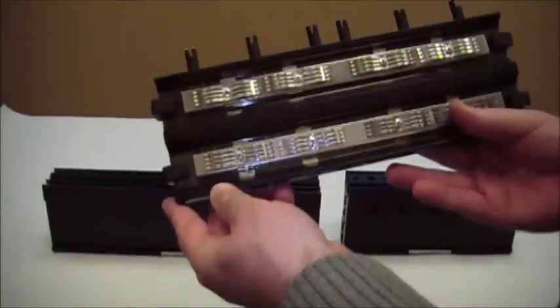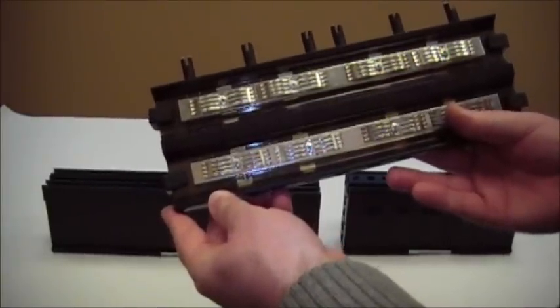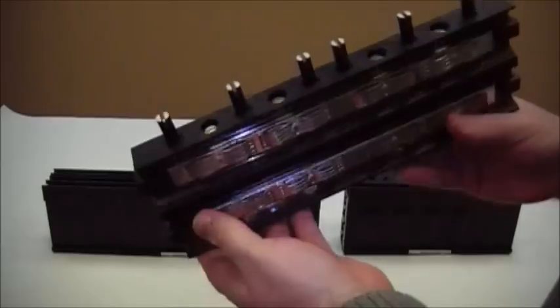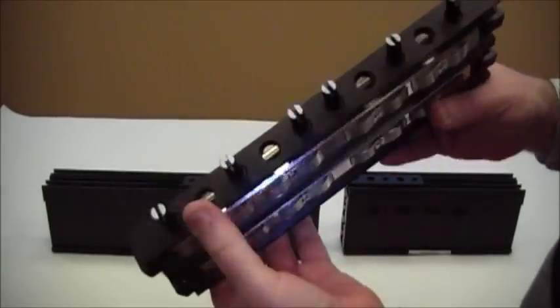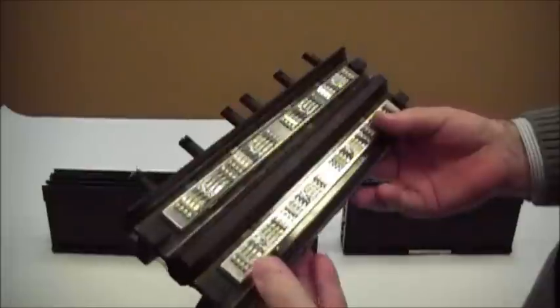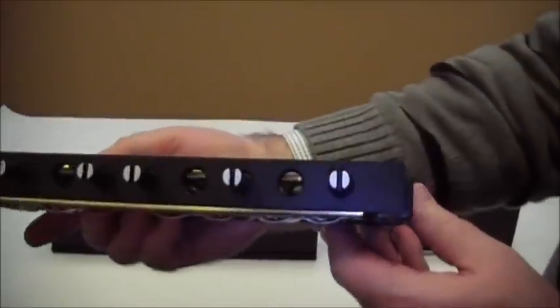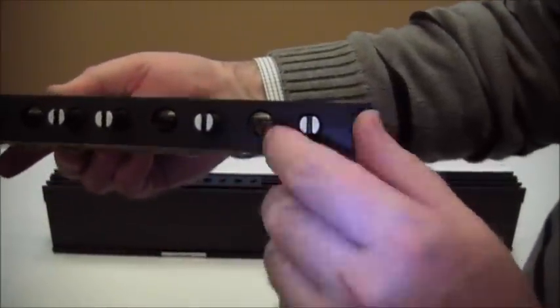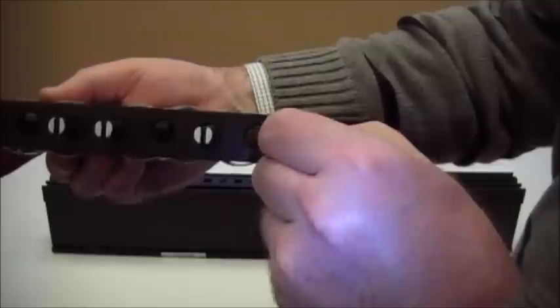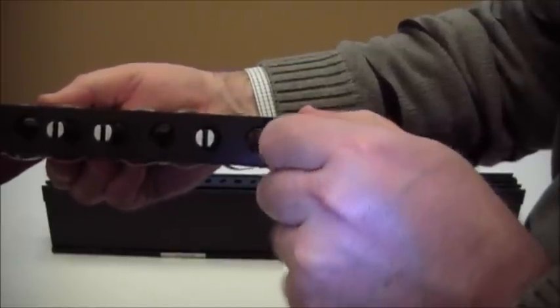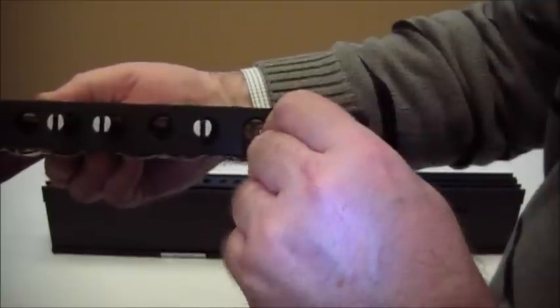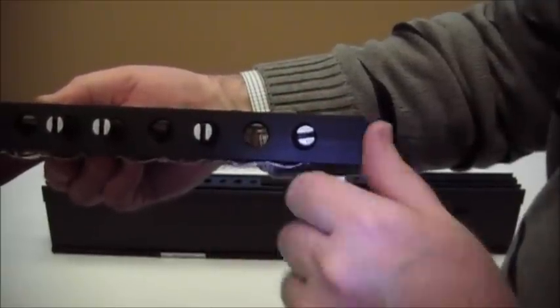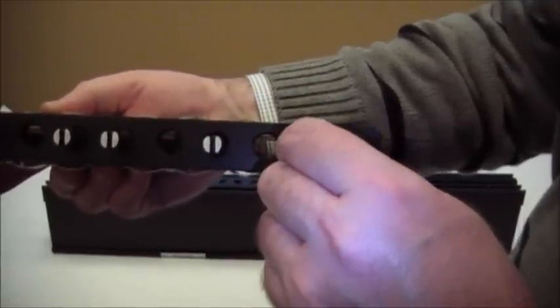The next step is to install the joint. You can see the joint kit here and it relies on pressing of the assemblies out into the bus bar when it's installed. As you turn those devices, it will spread the joint assembly and it will push up against the bus bar when installed.